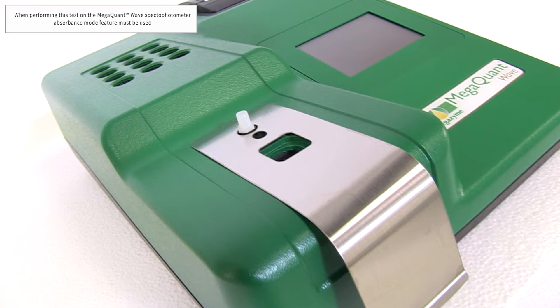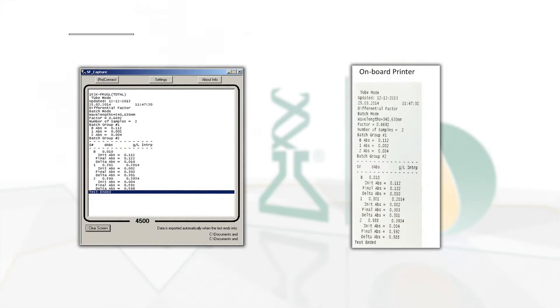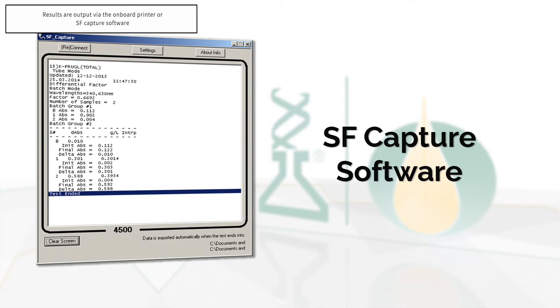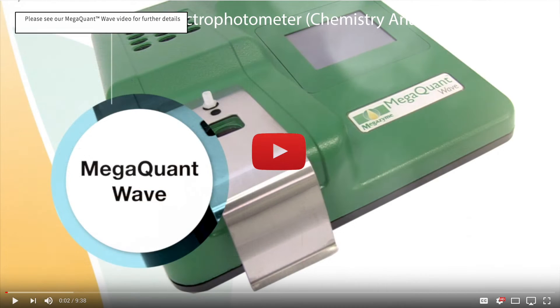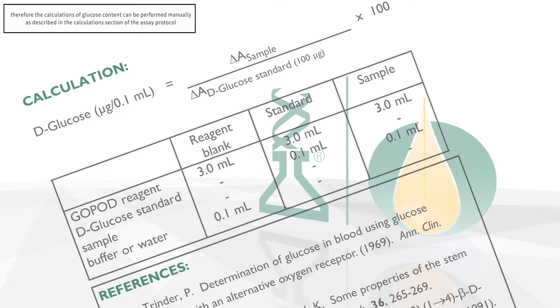When performing this test on the MegaQuant Wave spectrophotometer, the absorbance mode feature must be used. The results will be printed via the onboard printer or the data can be exported to a computer using the SF capture software. Please see our MegaQuant Wave video for further details. The absorbance readings of the samples, blanks and standards are used to calculate the D-glucose content in the test samples. In absorbance mode the results output are raw absorbance values for both blank and samples, therefore the calculations of glucose content can be performed manually as described in the calculation section of the assay protocol.